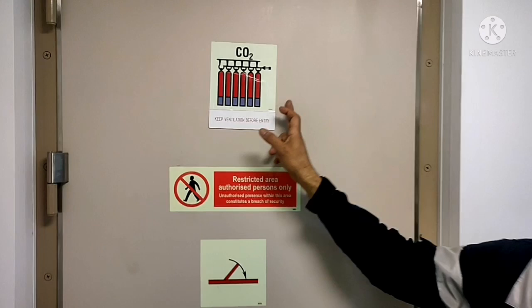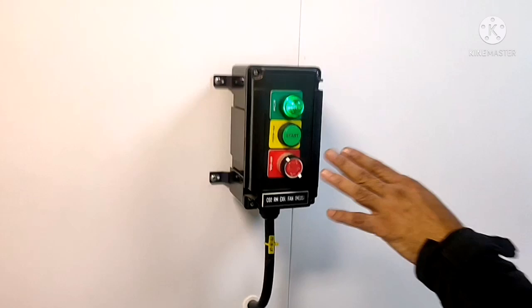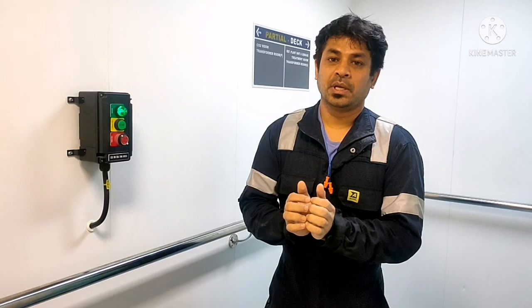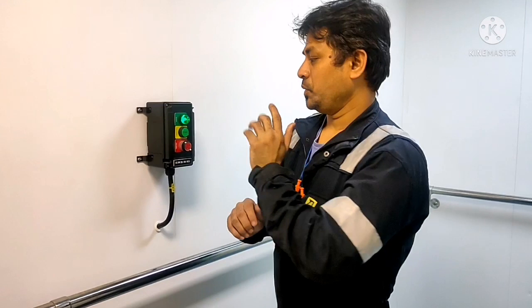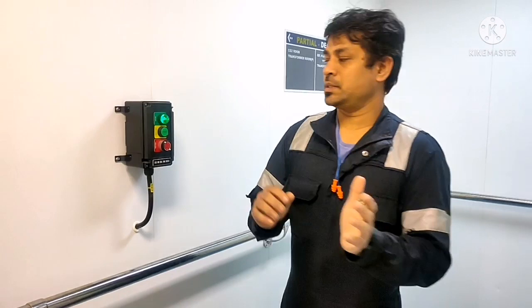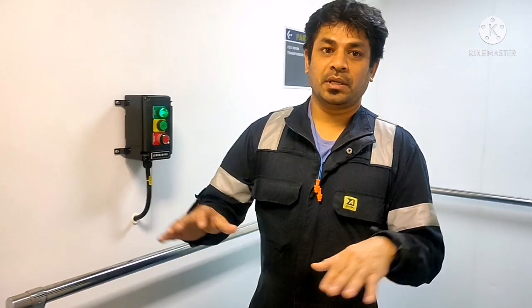This is your CO2 fire fighting symbol and this is your CO2 exhaust fan. This CO2 exhaust fan should run continuously at all times. Before entering the CO2 room you have to inform accordingly. The reason we need to keep the ventilation running at all times is that in case of any CO2 decay or leakage, it should not affect the person going inside. This ventilation can remove whatever gases have accumulated in the floor area of your CO2 room.